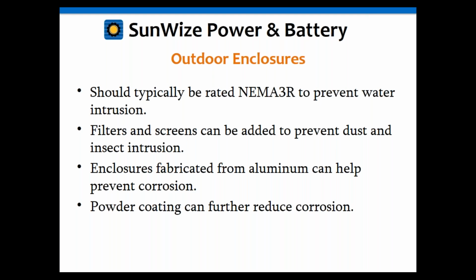Outdoor enclosures need to be a little more severe. Usually NEMA 3R type is what you're going to use. You normally don't want NEMA 4 because it's a sealed enclosure, though some applications may call for it, which I'll address in a minute. What you're trying to do is prevent water from getting in.